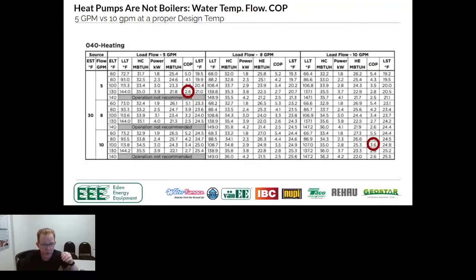I've pulled up an actual example for you. So if I looked at a scenario where I take, in this case, a 3.5-ton heat pump, and I'm going to feed it with the minimum flow. So you can see over here at 5 gallons a minute, that is the minimum flow for this unit. The recommended ideal flow is 10 gallons a minute. So could I make it work at 5 gallons a minute? I could try. I'd have to have a little bit of a battle of, is it going to lock out? Is it going to work properly? Or is it just going to run?